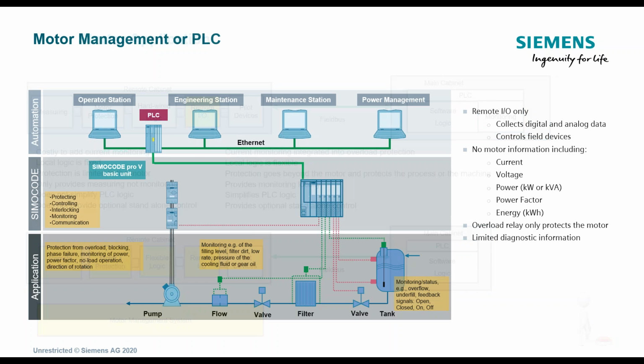Okay, motor management system. So here's just some simple applications that we want to walk through just to give you some ideas. So we have our remote I/O, we have our motor starter, and it's all wired up. We have a flow, a valve, a filter, another valve, and then we have a tank. Here we protect the overload. Here we're doing no load operation, direction of rotation, and so forth, monitoring the fill levels, the flows, the pressures, and so on. We have no motor information included at all. We don't have current, we don't have voltage, we don't have kilowatts, we don't have power factor, and so forth.